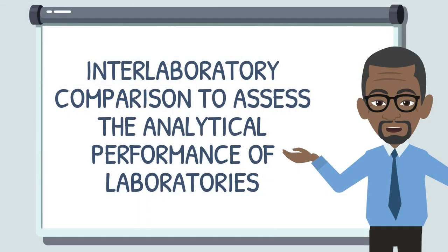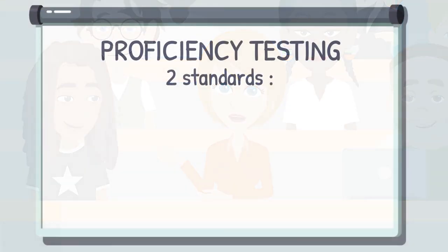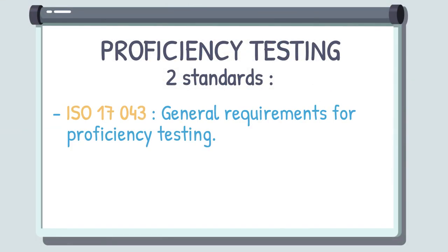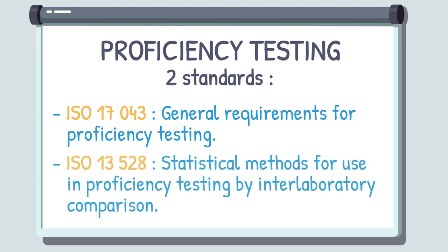If the purpose is to assess the laboratory's performance, the interlaboratory comparison is called proficiency testing. It is regulated by two standards: ISO 17043, General Requirements for Proficiency Testing, and ISO 13528, Statistical Methods for Use in Proficiency Testing by Interlaboratory Comparison.